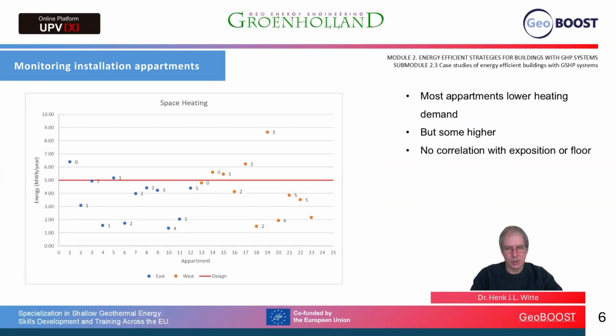Here, a result of the monitoring data of all apartments. What was really interesting to see is that almost all apartments have a heating demand, in energy in megawatt hours per year, used for space heating that is lower, and in a number of cases significantly lower, than the design value, which is the red line. At the same time, there are a number of apartments, 1, 2, and 3, that have a higher than design heating load in the same period.